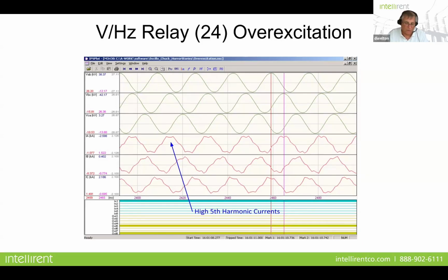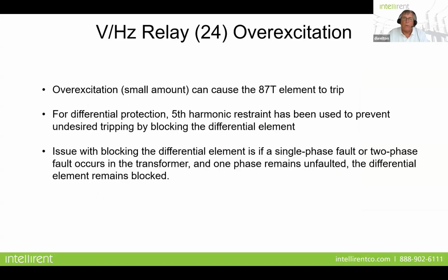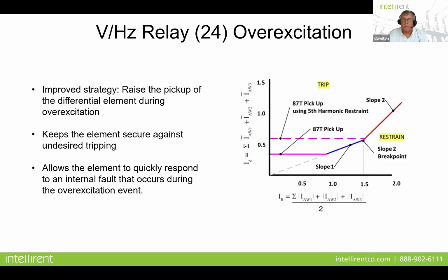And that's exactly what it's there for, to keep the differential from tripping should you have a small overexcitation event. So overexcitation can cause the 87 element to trip, and for that purpose, we use fifth harmonic restraint, and the issue with blocking the differential element is if a single phase fault or two phase fault occurs in the transformer, and one phase remains unfaulted. The differential element's going to remain blocked, okay?